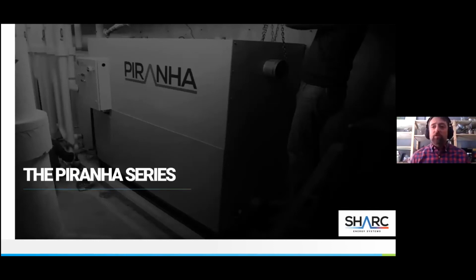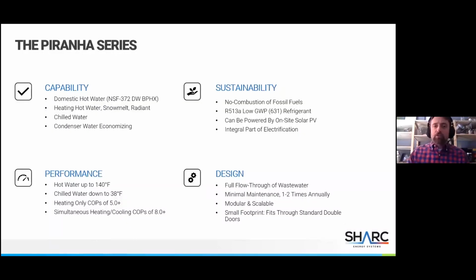As far as that equipment is, we've got two series. We've got a smaller series that's more of a building scale. And then we've got a larger series that's more for the district energy system type stuff that you've heard a little bit about. I'll start with the smaller, the PIRANHA series. Basically, it's a packaged heat pump water heater that's using raw wastewater as its source. So you heard Carl talk a little bit about heat pumps taking heat from a source. That's what this is doing: it's taking that heat from the raw wastewater and then transferring it into refrigerant.